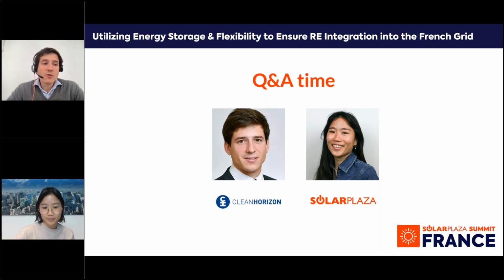So if you want to handle all this data properly, knowing that a battery storage system can respond in about 300 milliseconds typically, you need to monitor this every second at least. That's a tremendous amount of data that you need to share, collect, store, and analyze. So that's probably one of the big challenges.